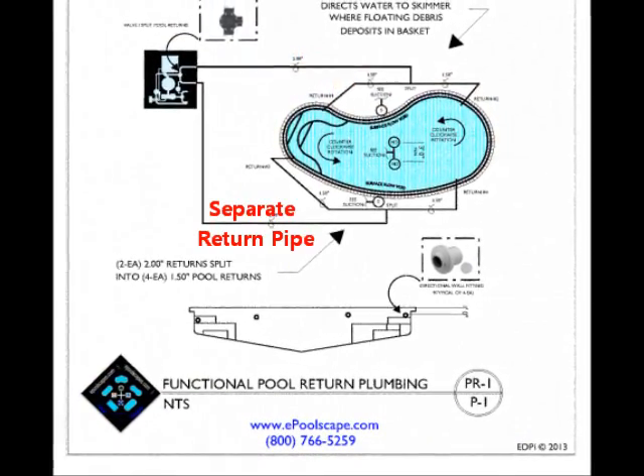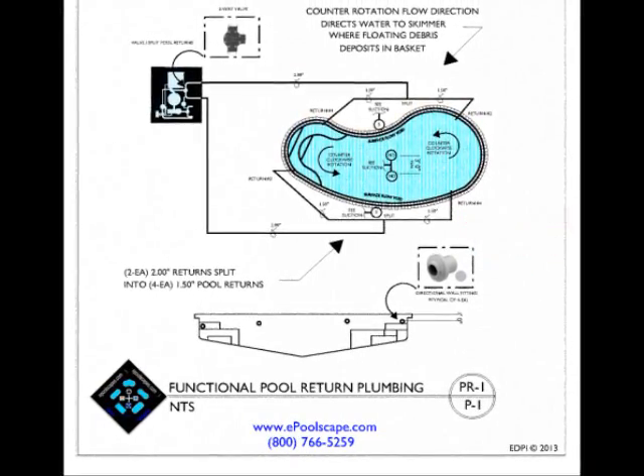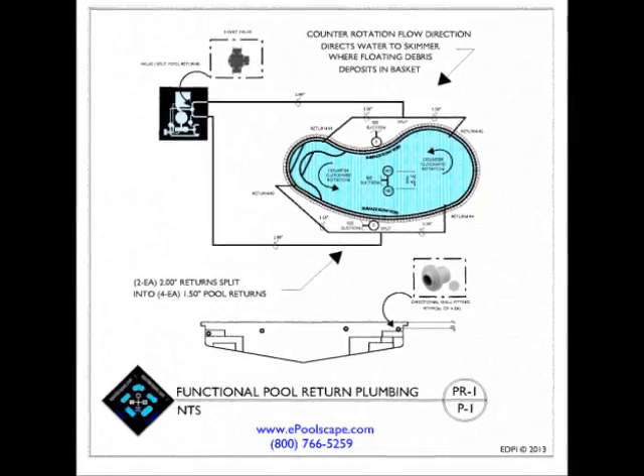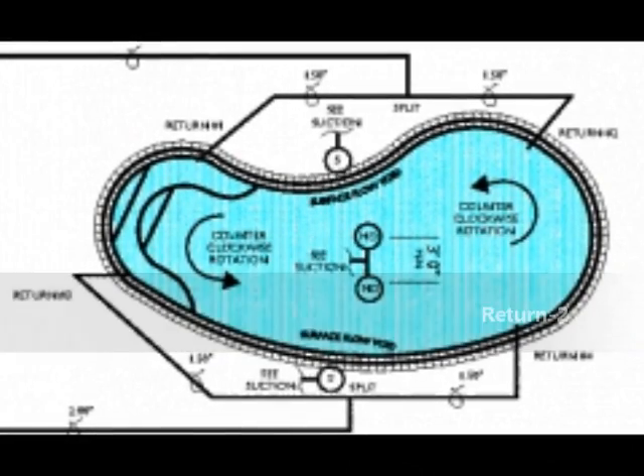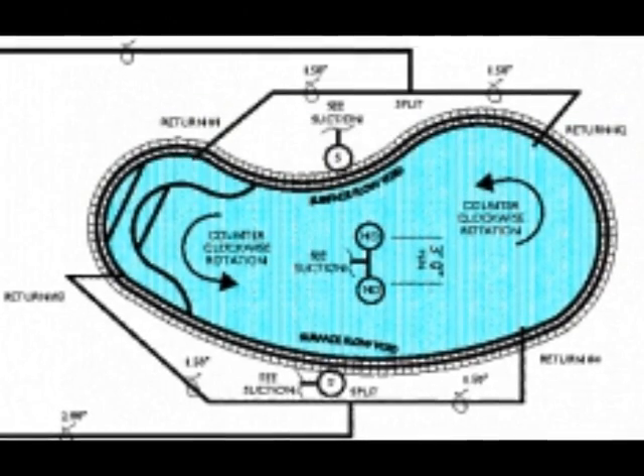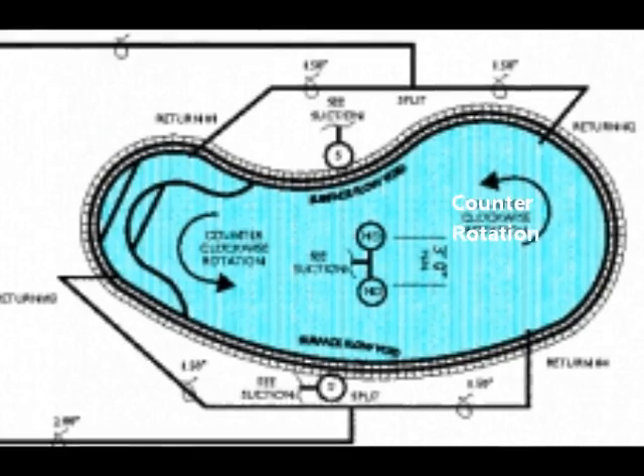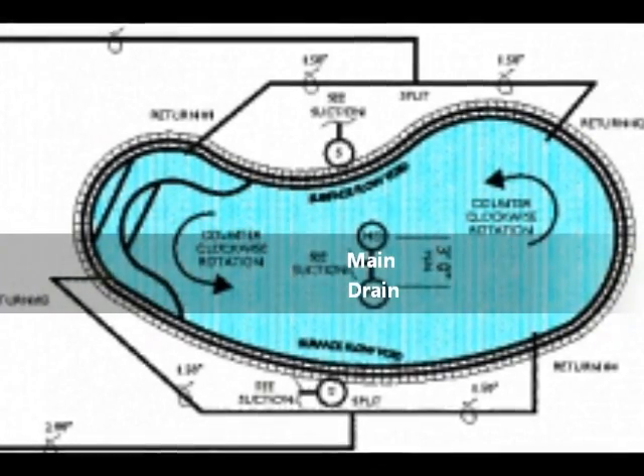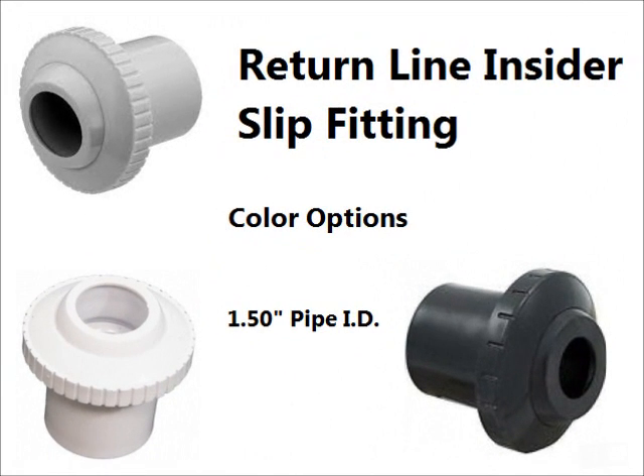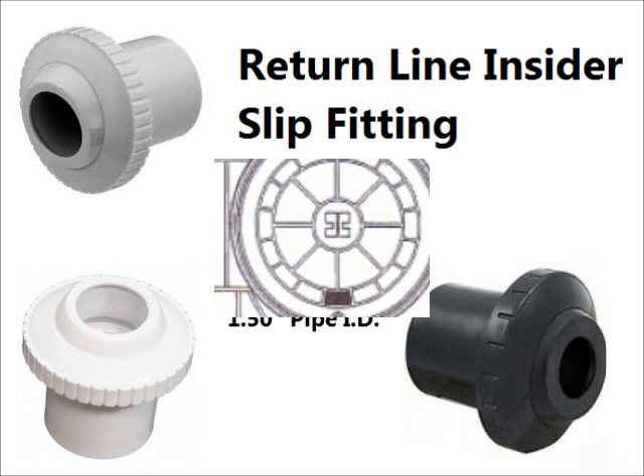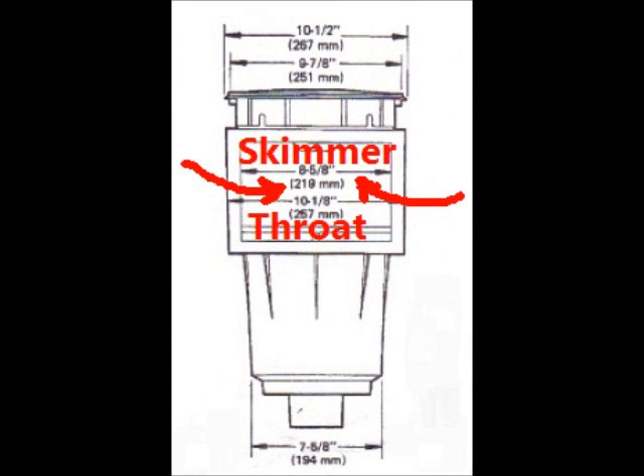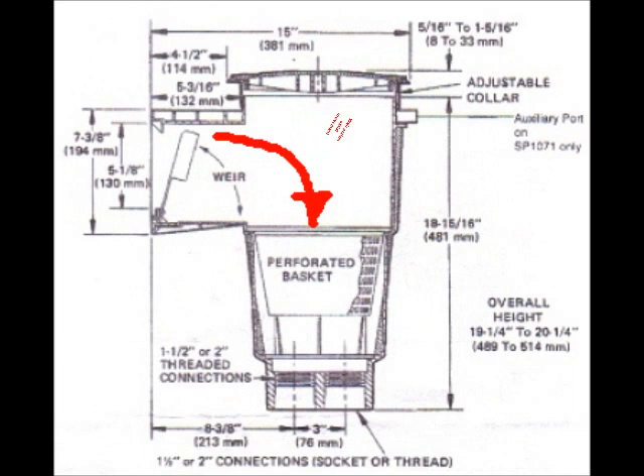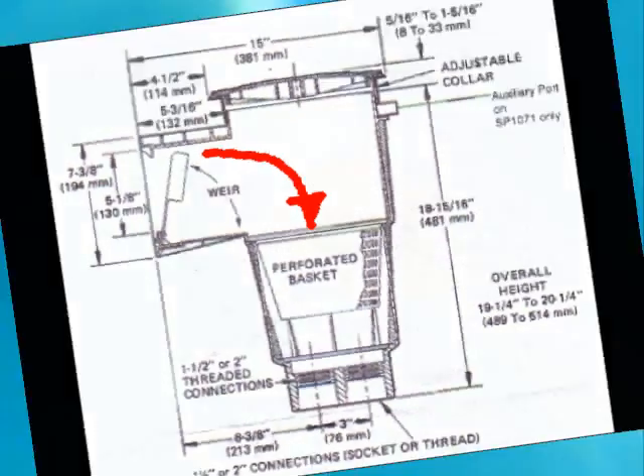The other half of the swimming pool's plumbing system involves the return lines. In delivering water back to the pool, it should consider how the returning water flow will affect surface action and become part of the determination for positioning the surface skimmers. Although the general rule of thumb is to have one skimmer device for approximately every 500 square feet of pool space, some pool configurations may adversely affect the returning water and diminish the desired results. The objective is to place the return lines in a fashion that creates a counter-rotation water movement on the surface at the intersections where the throat of the skimmers are located, resulting in a slight lull in flow, thus allowing the surface skimmer's suction to overcome the surface flow and draw floating debris into the interior leaf basket.